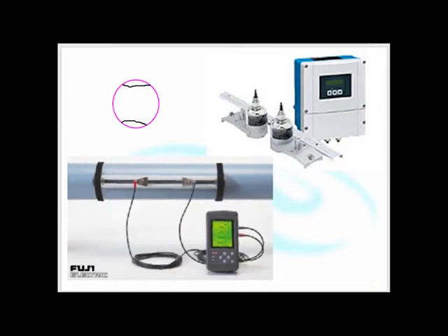So you have to make sure, if you do have air bubbles or slurry, that you mount the sensor on the side so that it's not going to be affected by those air bubbles. Anything inside there that can absorb sound will stop it working. Like I say, it's not especially accurate.